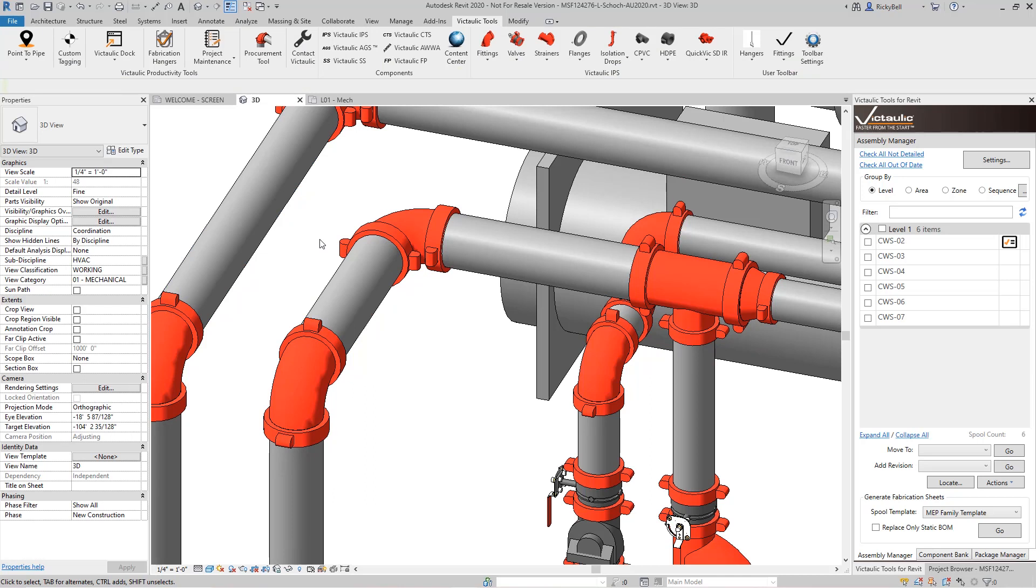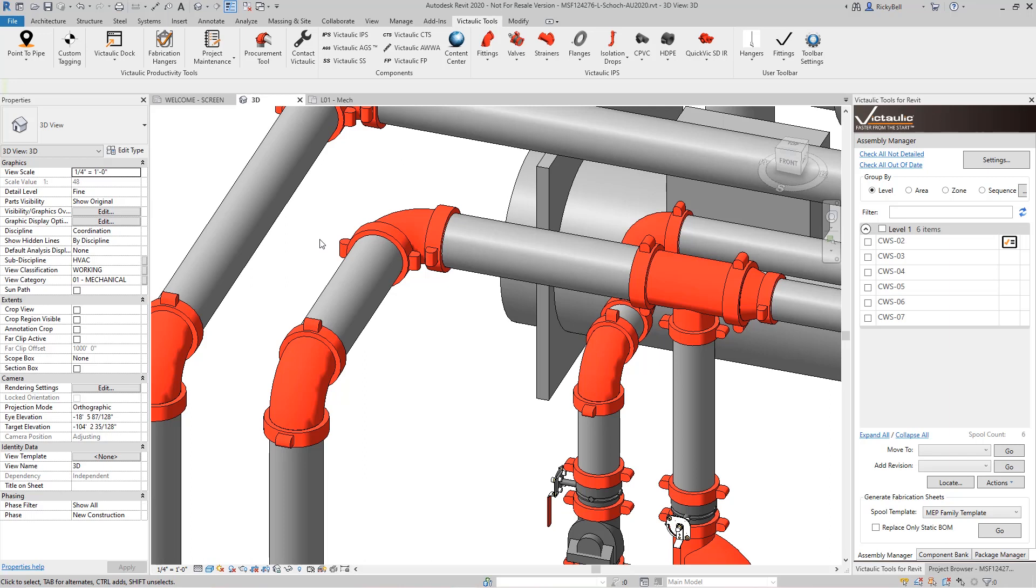One thing you can't do with Revit's new tool is select any other category at the same time. So if you have multiple trades on the same hanger, then you're going to be setting them individually. Another thing the Revit tool doesn't account for is insulation on the pipe. When you set the elevation by the bottom of the pipe, the insulation gets ignored and becomes a conflict with the hanger.